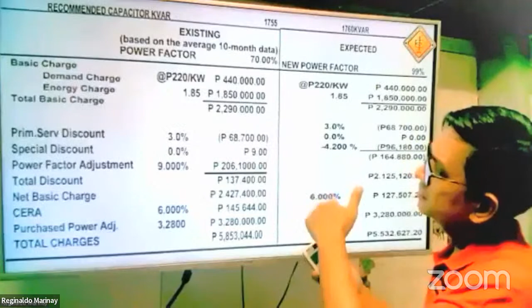Let's continue. Why does this become 9%? How did you get that? You just have to subtract 85% minus 70%. Put the 85 first, then minus the existing power factor, which is 70%. That is obviously 15. So there is a 15% difference in power factor, lower than 85%. What is the unit of this 15%?